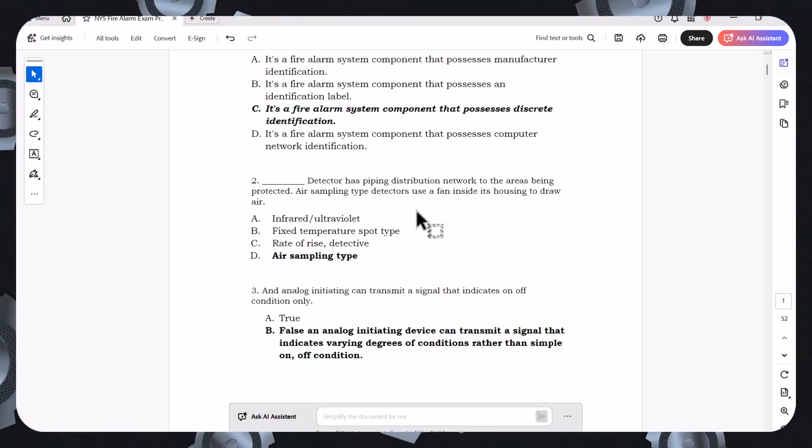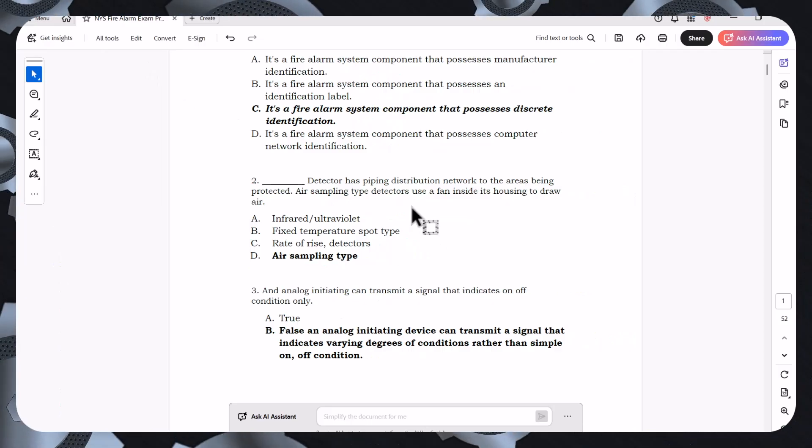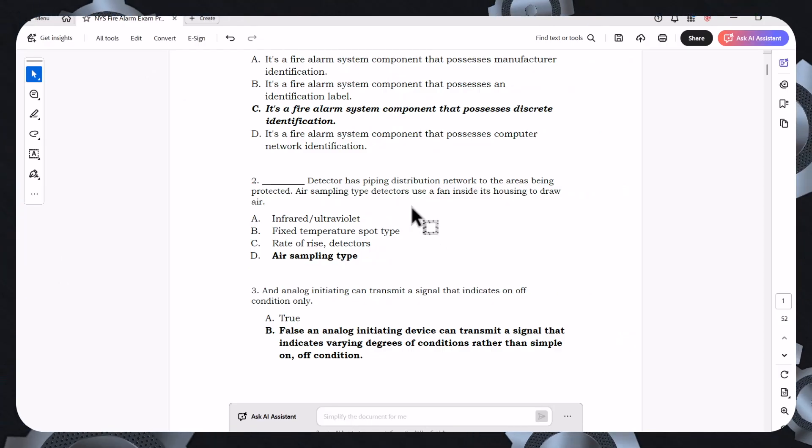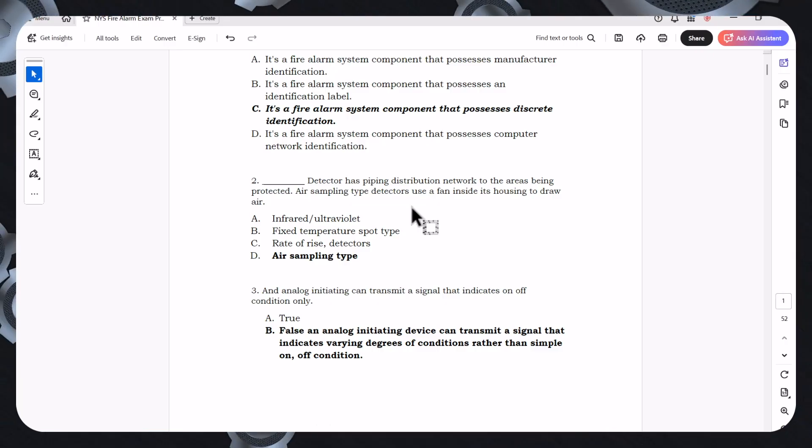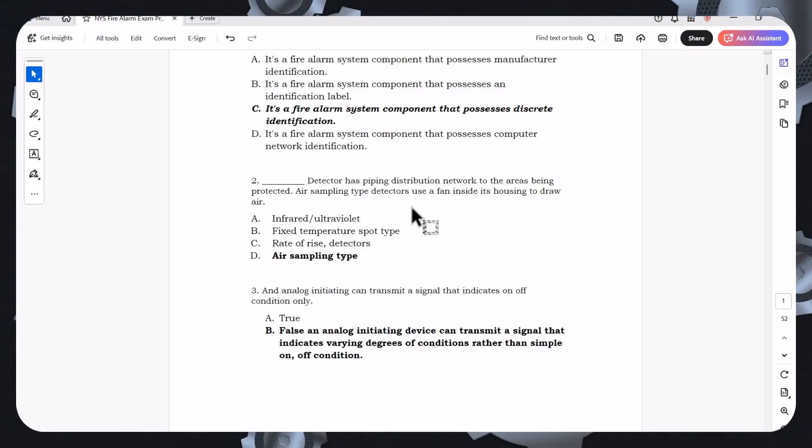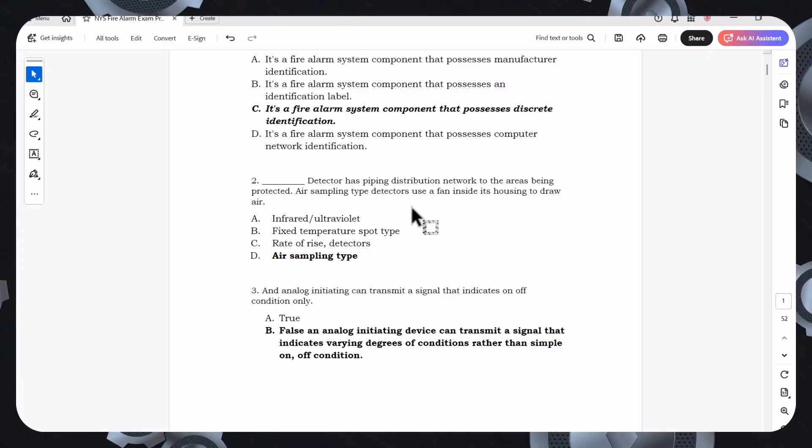We have fixed temperature spot type detectors, rate of rise detectors, or air sampling type detectors. So the best possible answer there would be an air sampling type detector that has piping distribution. That would be like a VESDA system, something like that.